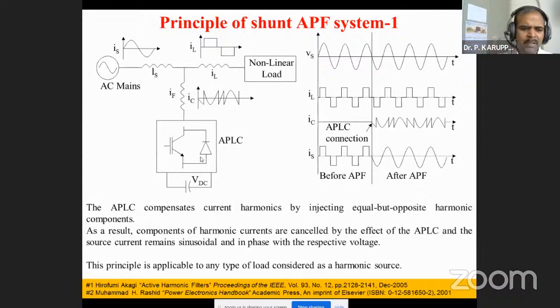The compensation current cancels the harmonics and maintains the current always sinusoidal with respect to the load current. The APLC compensates current harmonics by injecting equal but opposite harmonic components. As a result, the harmonic current components are cancelled by the active power line conditioner, and the source current remains sinusoidal and in phase with the voltage. This principle is applicable to any type of load considered as a harmonic source.